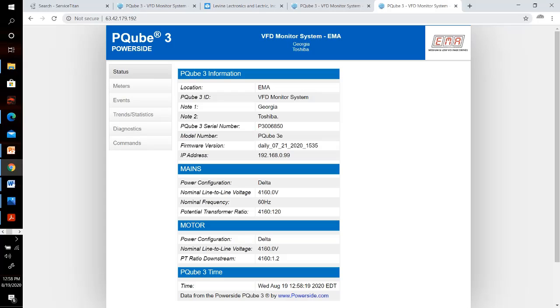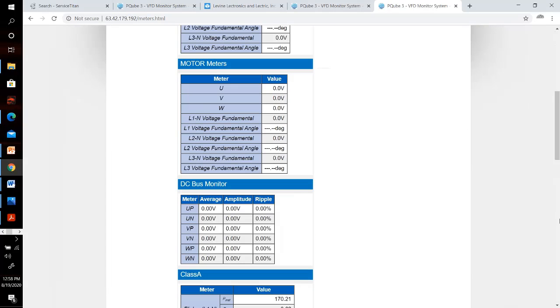It will manifest itself either by leaking the electrolyte out of the can, which then also manifests itself as ripple because now we don't have as much electrolyte inside the can, or it dries out. Sometimes it doesn't even leak out, it just dries inside the can, and again that manifests itself as ripple. So we are continuously monitoring the ripple ratio with drive scan, and by doing so we can actually know about a failure before it happens.